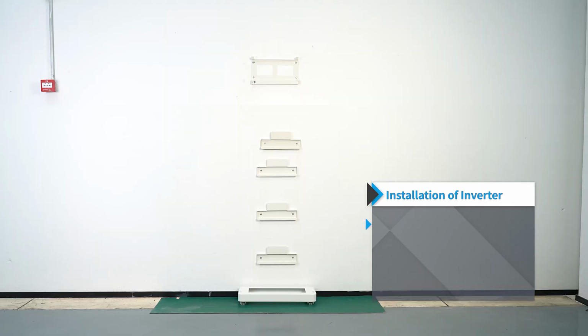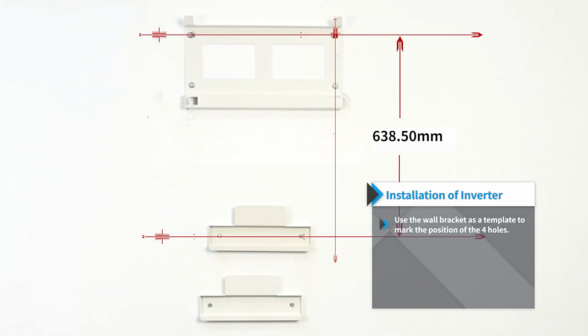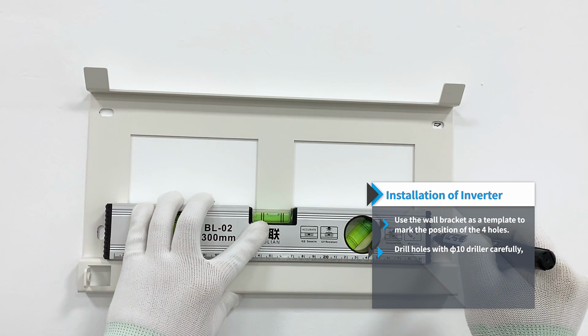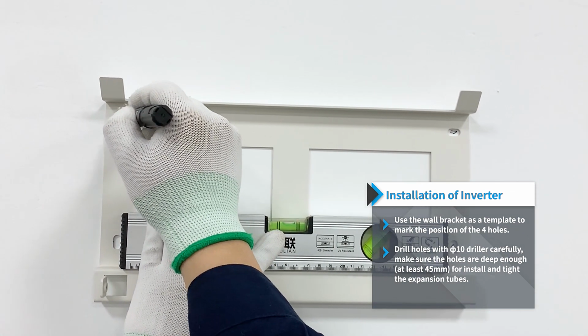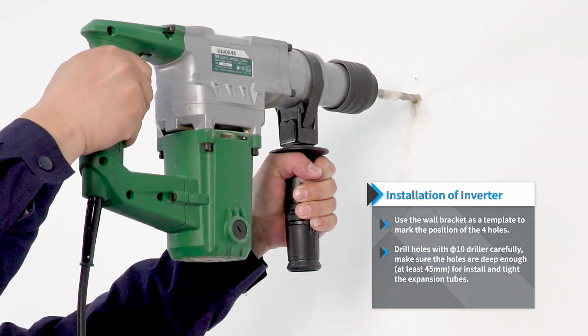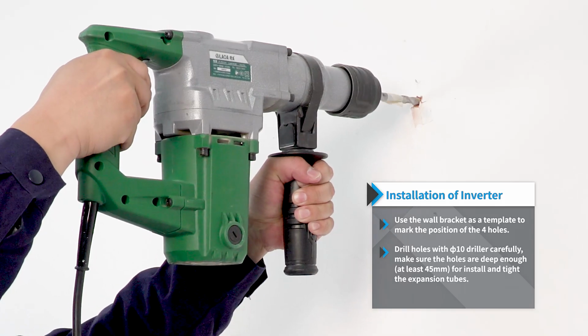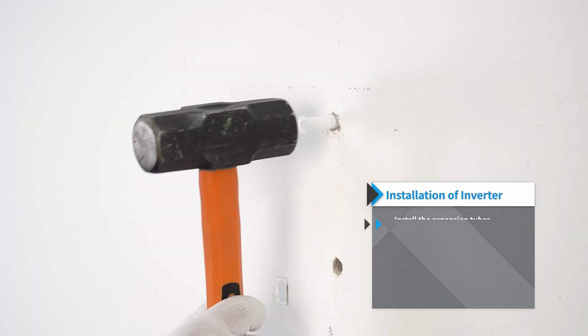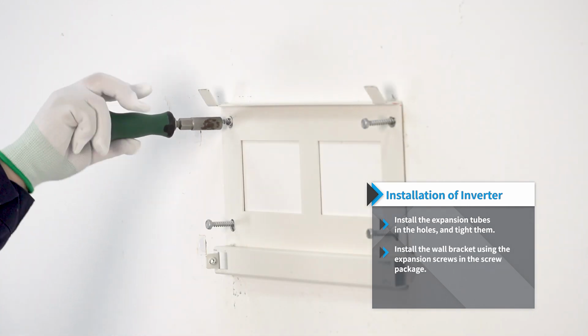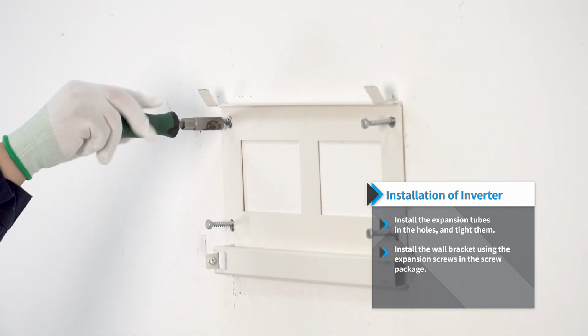Installation of inverter: use the wall bracket as a template to mark the position of the four holes. Drill holes with a 10 drill carefully, make sure the holes are deep enough, at least 45 mm, for installing and tightening the expansion tubes. Install the expansion tubes in the holes, and tighten them. Install the wall bracket using the expansion screws in the screw package.